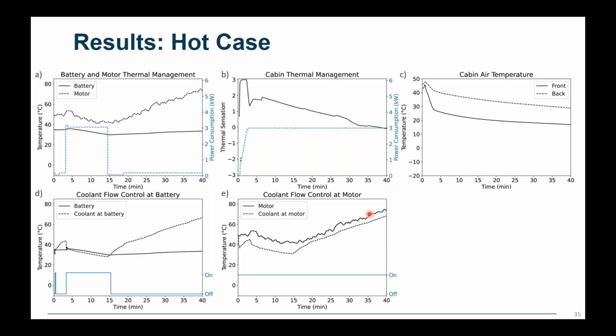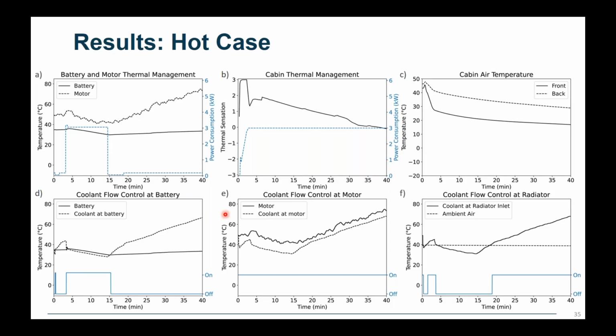For the motor, since the motor is the hottest component of our system, the coolant always stays below the motor temperature, so we always flow the coolant past the motor. And at the radiator, the air temperature is also quite hot, so we have situations where the ambient air temperature is hotter than the coolant temperature, and in that case we turn off the coolant flow through the radiator, so we are not heating the coolant with the outside air.